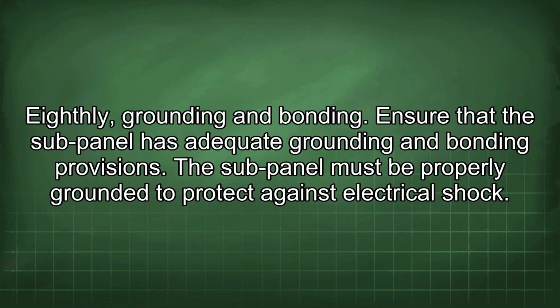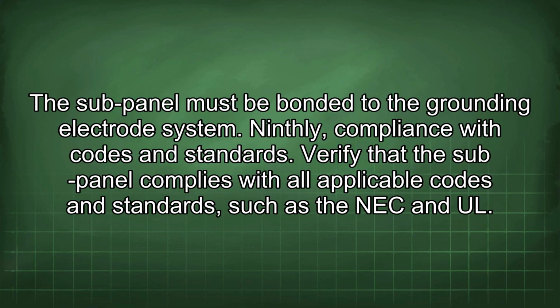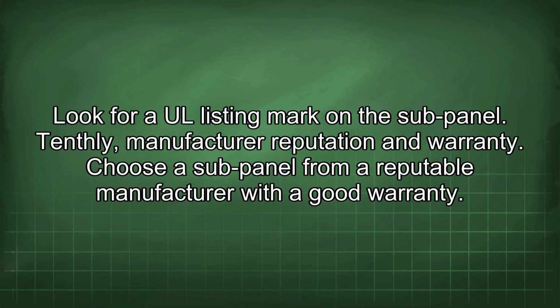Eighthly, grounding and bonding. Ensure that the sub-panel has adequate grounding and bonding provisions. The sub-panel must be properly grounded to protect against electrical shock. The sub-panel must be bonded to the grounding electrode system. Ninthly, compliance with codes and standards. Verify that the sub-panel complies with all applicable codes and standards, such as the NEC and UL. Look for a UL listing mark on the sub-panel.